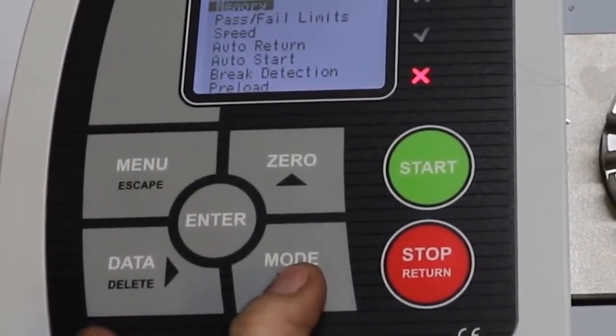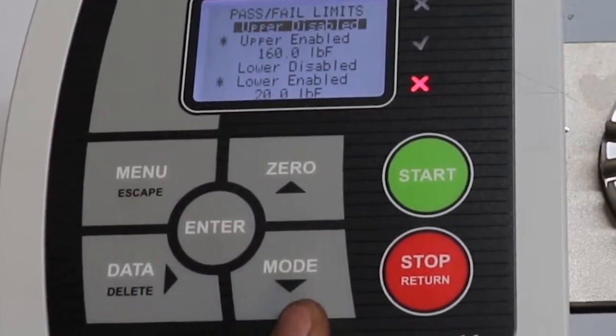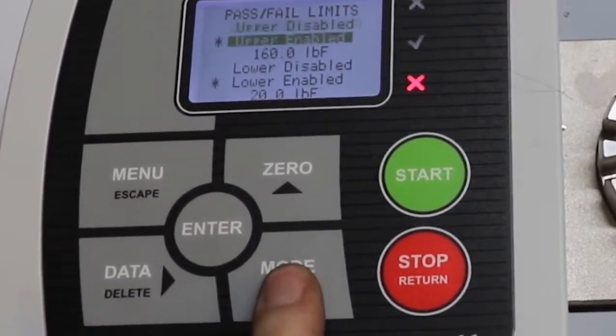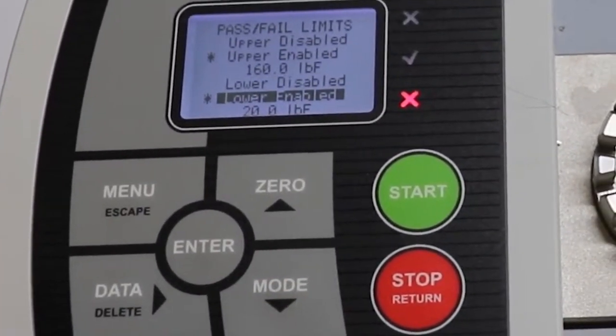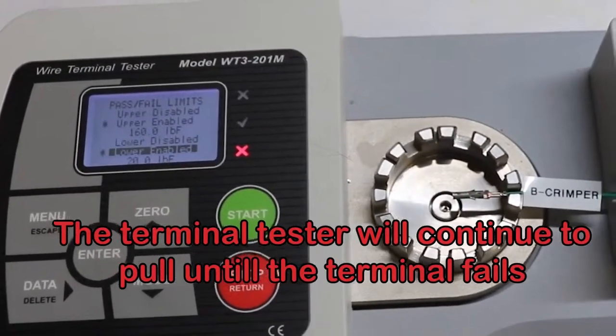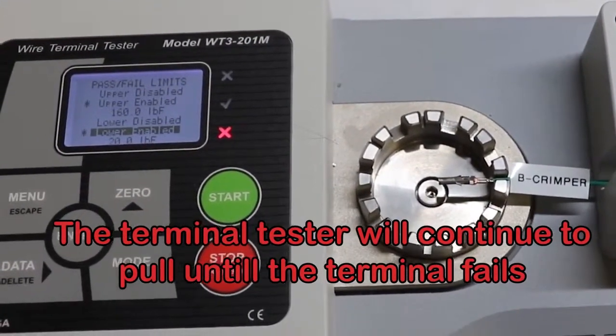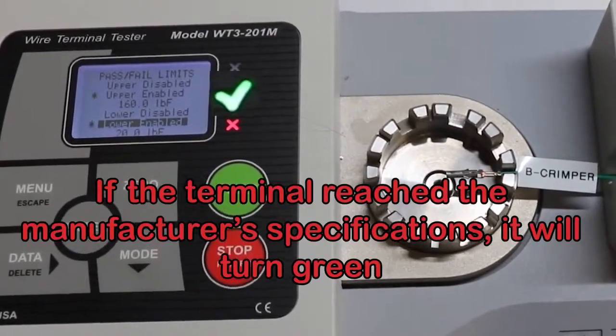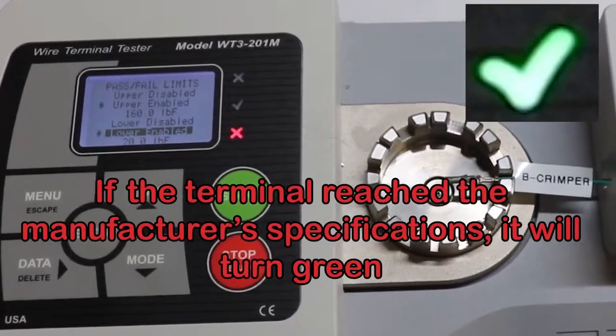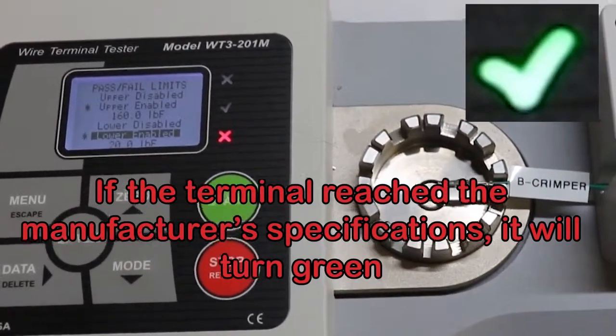Go down to pass and fail limits. Okay. We want to go down to lower enabled. Okay, and where are you getting this lower enabled number from? You'll go directly from the manufacturer, who will have a specific pull force that they want you to test and pass. Okay, so we do have a pass fail limit and that's provided by the manufacturer. Yes, yes it is.